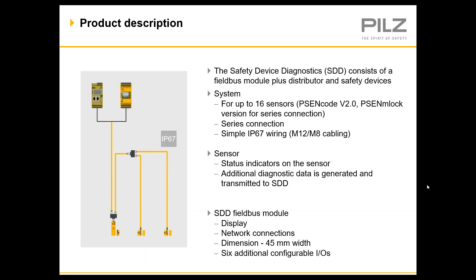To illustrate this, a system can support up to 16 sensors, each sensor having eight wires. That means in a system with 16 sensors, there would be 128 individual connections that would have to be routed back to the main panel and wired to individual terminal blocks. M12 cabling instead would mean using just 16 quick-connect M12 cables. Sensor status can be obtained on the device itself, read from the display on the SDD, or from third-party devices connected on the network. Six configurable general purpose I/O are also available, and their use is highlighted in one of the examples later.